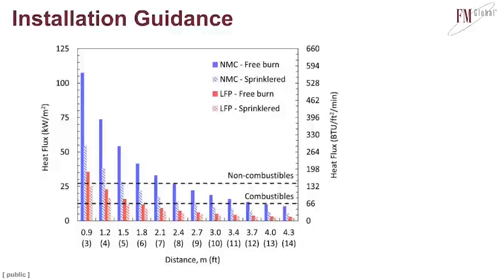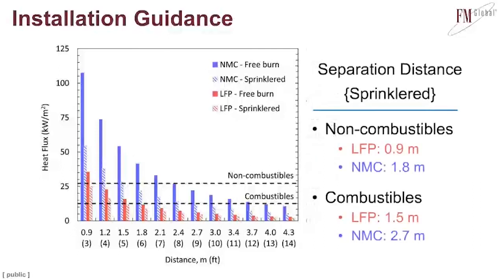Here I'm showing on the vertical axis the heat flux. This is the amount of energy that's being pushed to my surroundings, and I'm showing that as a function of distance from the fire. And because I have all the different measurements of heat flux, I can do this in a fairly confident manner. So if we look at this, for example, let's look at the NMC free burn data, which is the solid purple lines. If you look where it says 3 feet, you can see that the heat flux was somewhere over 100 kilowatts per meter squared. That's a very high number.